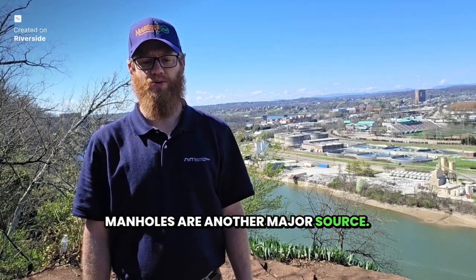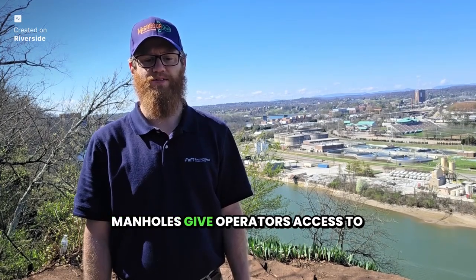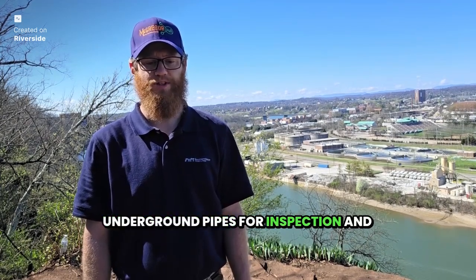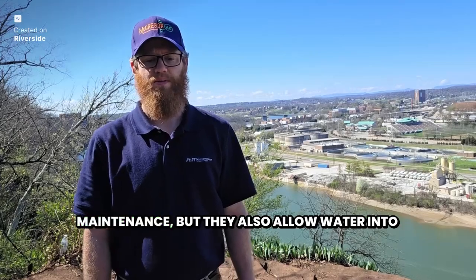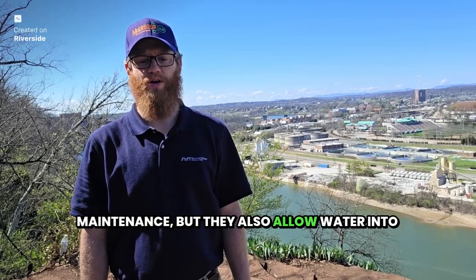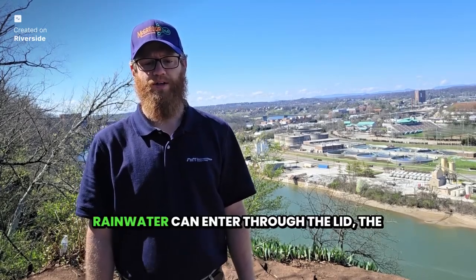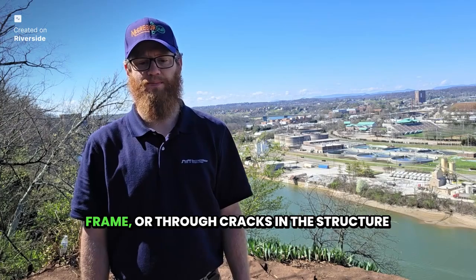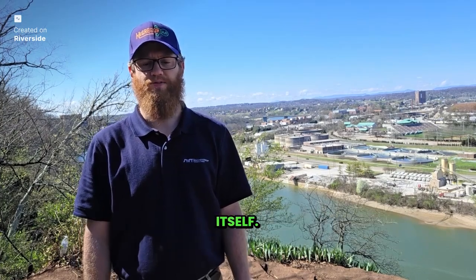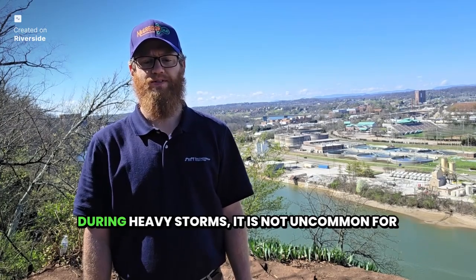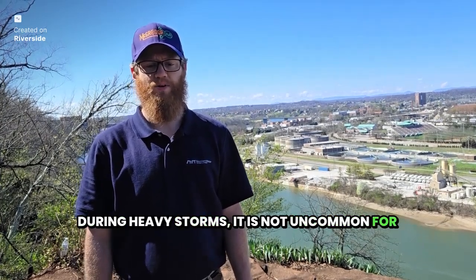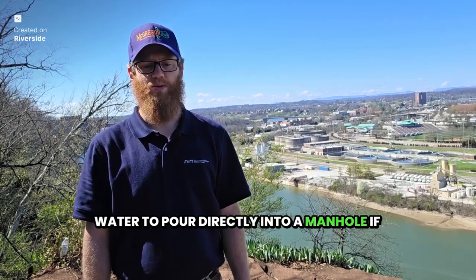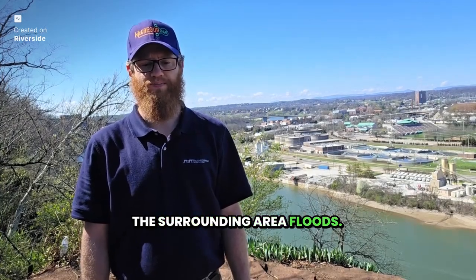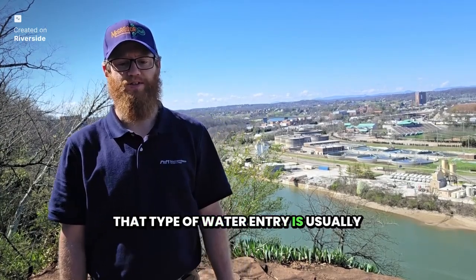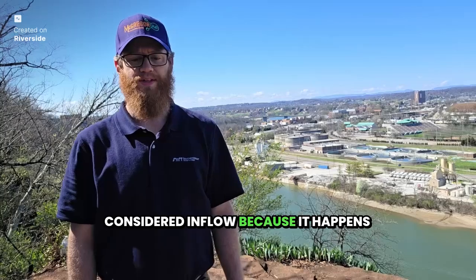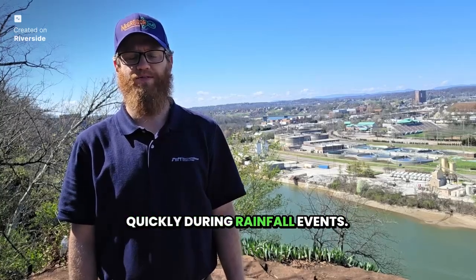Manholes are another major source. Manholes give operators access to underground pipes for inspection and maintenance, but they also allow water into the system. Rainwater can enter through the lid, the frame, or through cracks in the structure itself. During heavy storms, it is not uncommon for water to pour directly into a manhole if the surrounding area floods. That type of water entry is usually considered inflow because it happens quickly during rainfall events.